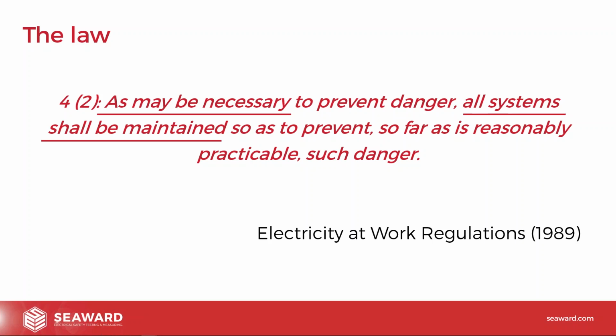But what we do to check where the maintenance is required is we carry out what we know as portable appliance testing, an inspection and testing of equipment. So when we're looking at this, we're not just looking at the electrical safety of it. It's not just a quick beep beep on the PAT tester and there you go. Obviously, we'll do detailed visual inspections, we'll do functional tests, all of those sort of things. And we are looking for maintenance.